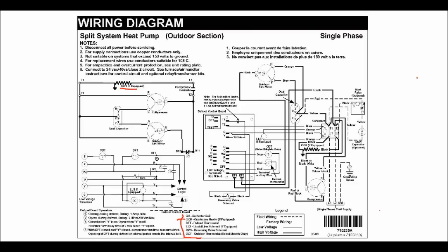And then let's look down here, CC, what is this? Look down here at the bottom, and you see that that stands for contactor coil. So while all of the manufacturers don't standardize schematics, they will all have legends, and they will all have a little decoder down here that shows you what the abbreviations stand for.